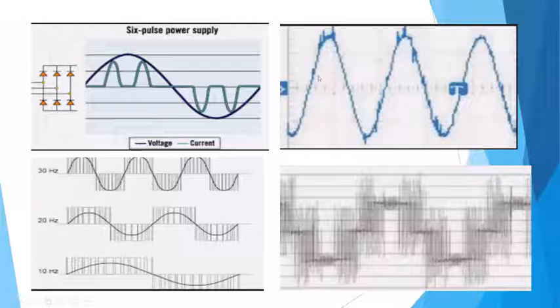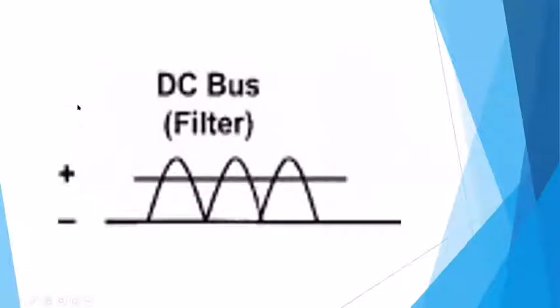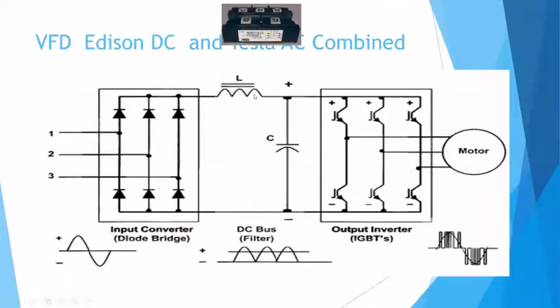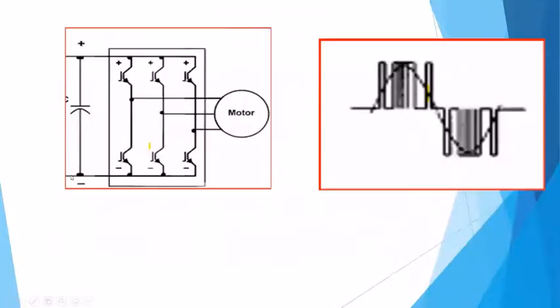The issue, though, is that if you look at the voltage input here, you've got to watch these peak to peak voltages that come about just because of the wire and the capacitance going into the circuits. So you'll get these higher jagged voltages. Well, this then creates noise back on this front power line. So what they want to do here is put inductors here, or like I was showing you earlier, put an inductor inside here. And that basically gives us the ability to compensate for some of that high frequency that's developed.